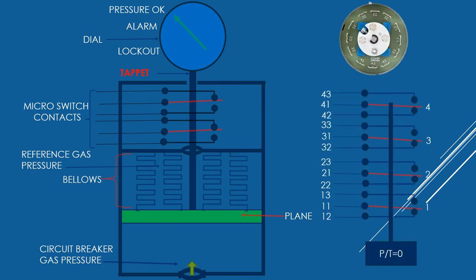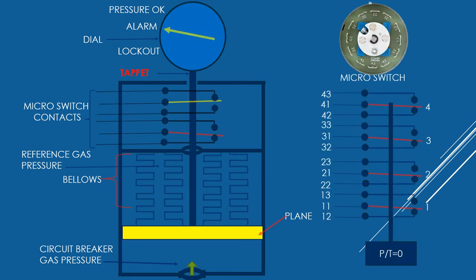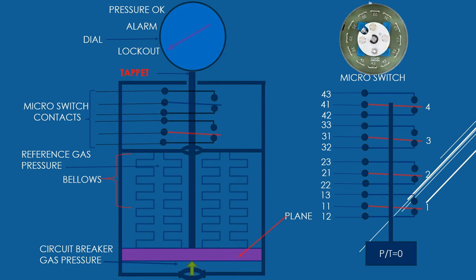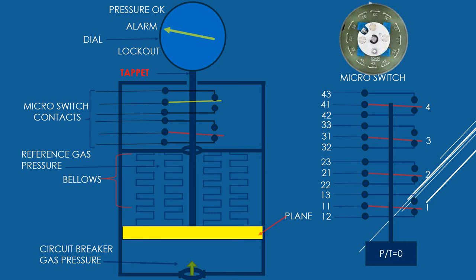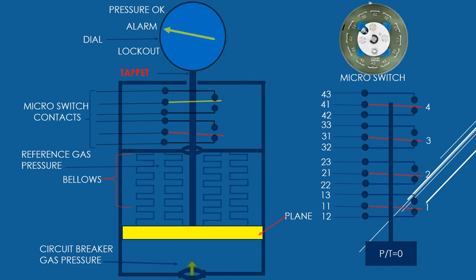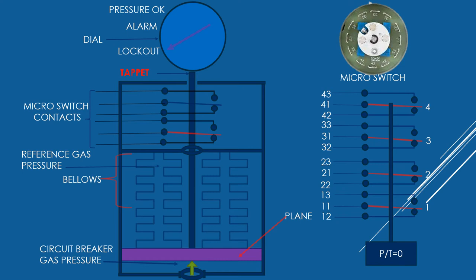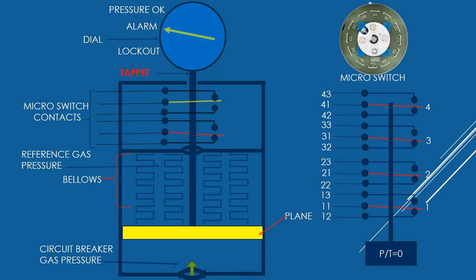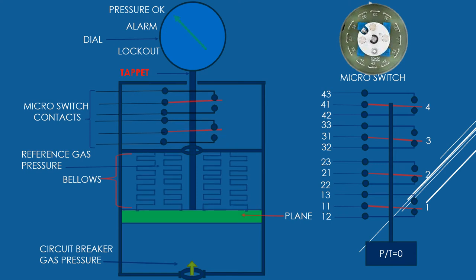Micro switches are operated by a tappet or lever which moves either to disconnect a circuit or to connect the circuit. The tappet is set on the plane separating the reference gas pressure chamber and circuit breaker gas pressure chamber, and can move freely up and downward according to movement of the diaphragm to make and break contacts on the micro switch. Any decrease or increase of pressure inside the circuit breaker pole is compared, so the tappet moves up and downward according to contraction or expansion of the bellows.